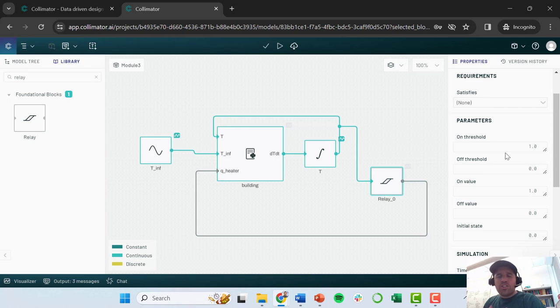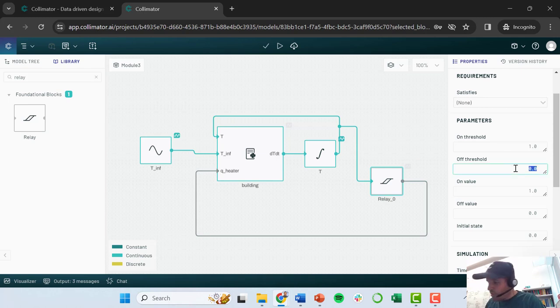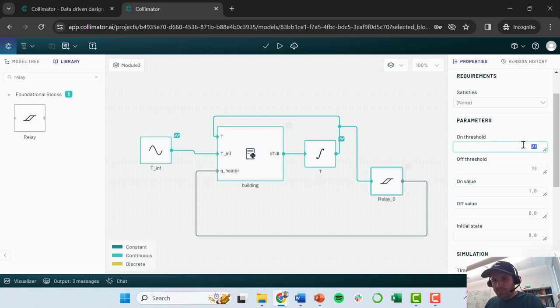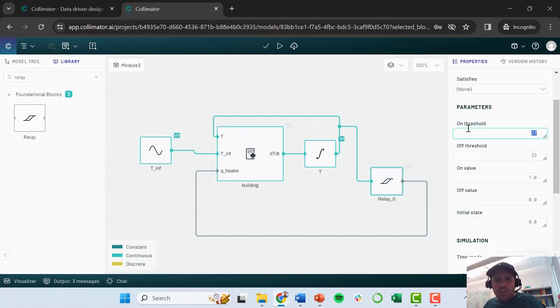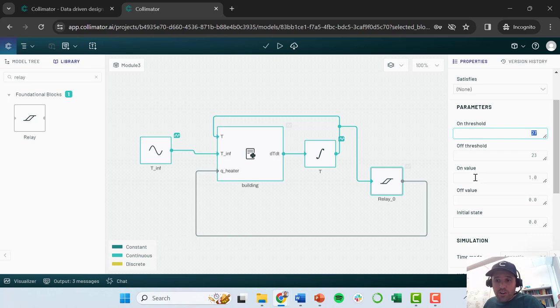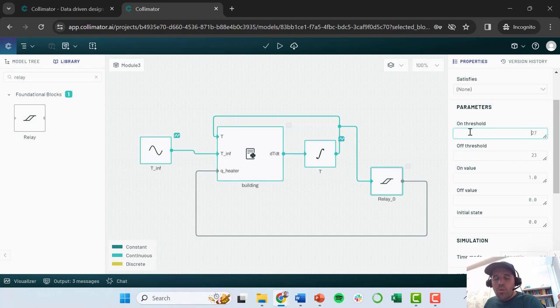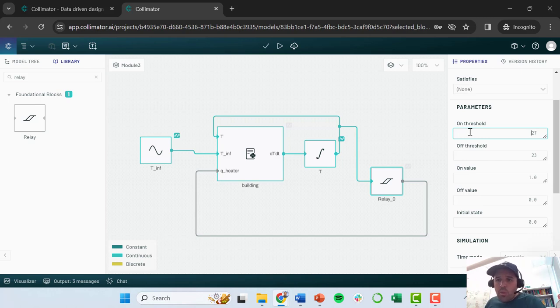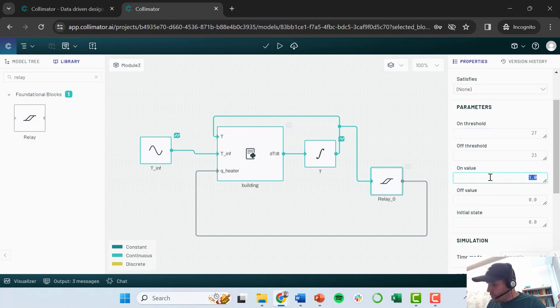And then the block itself is going to retain in memory what the value of your previous heater position was before. So what we want to do is give this these parameters. So in collimator we want to give this a lower threshold and an upper threshold. So instead of just controlling to 25 degrees Celsius I'm going to control between 23 degrees and 27 degrees. And you'll have to ignore. So collimator gives you by default this on threshold and off threshold. We're going to kind of ignore those. But basically when we hit this upper threshold. This on threshold. We want to determine what we want the value of our heater to be in that case. So when we as our building temperature rises and we hit this upper threshold. We want our heater to turn off. So we want when we hit that upper threshold. We want our heater to have a value of zero.